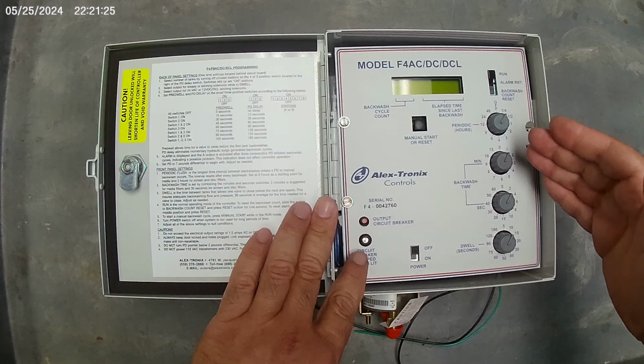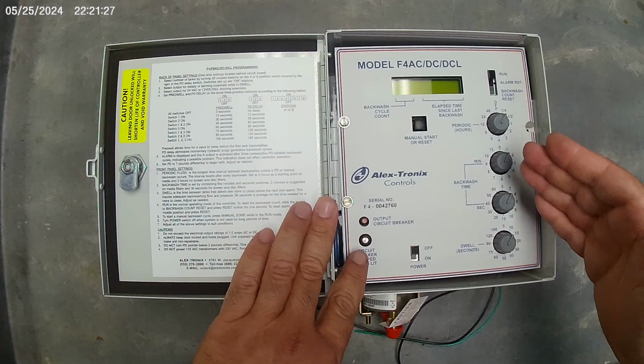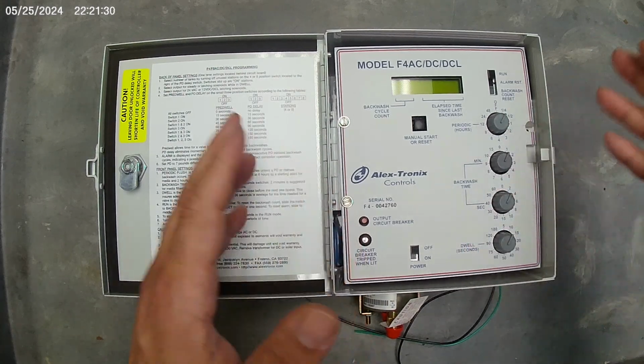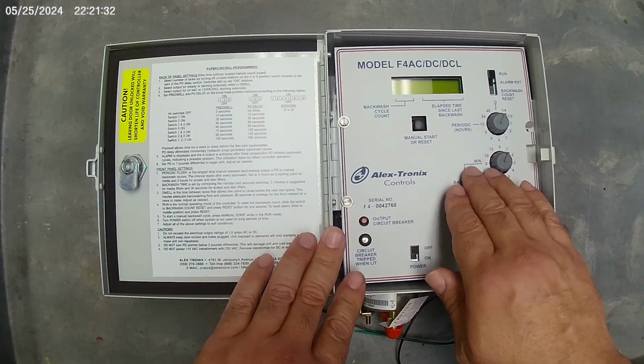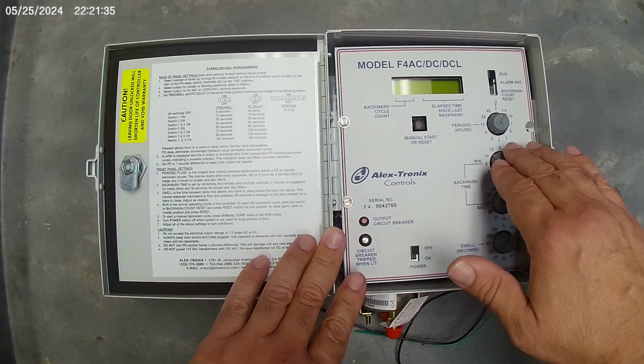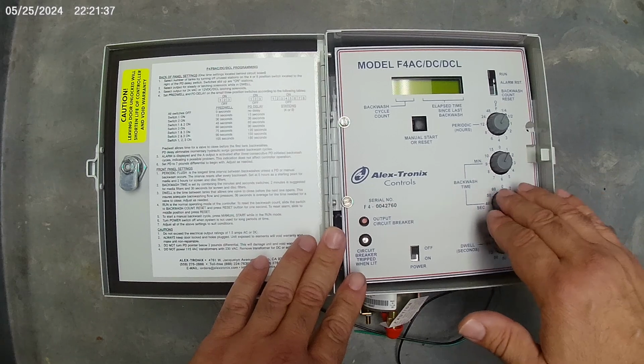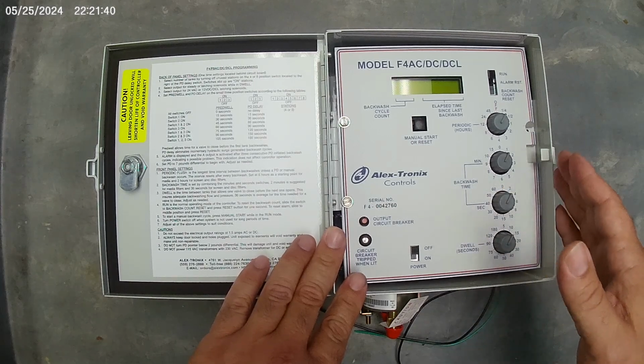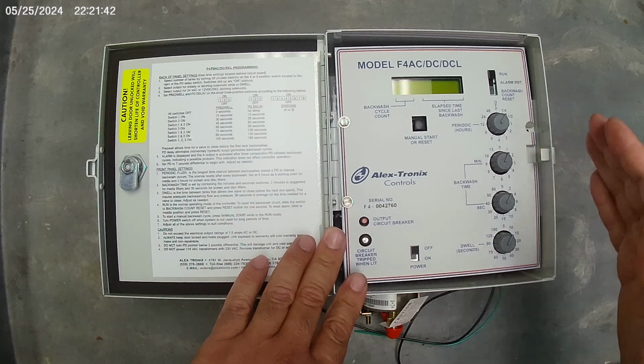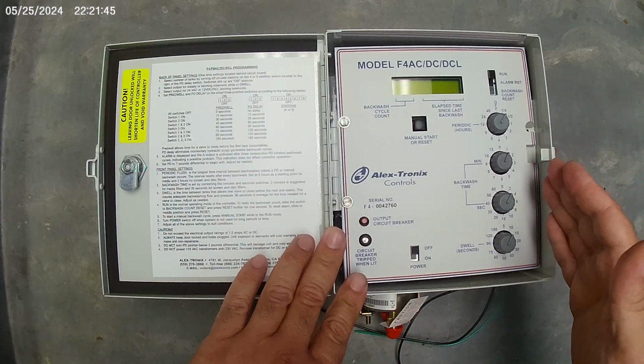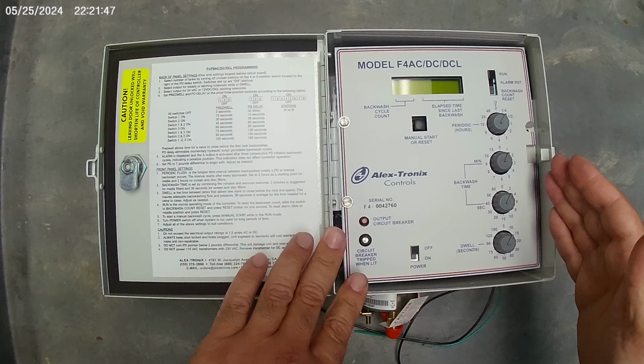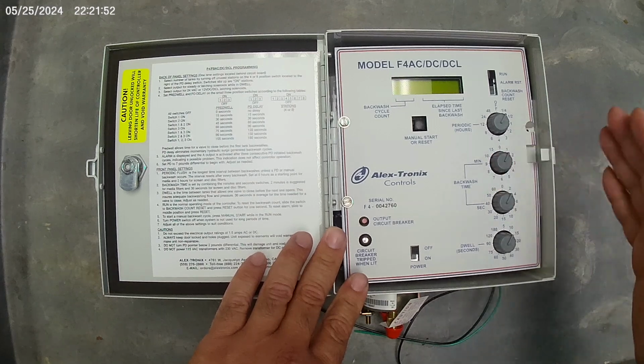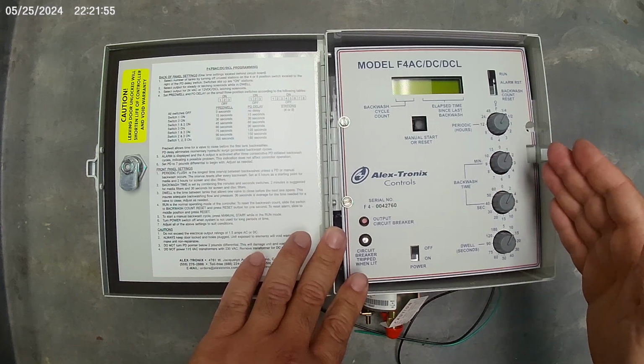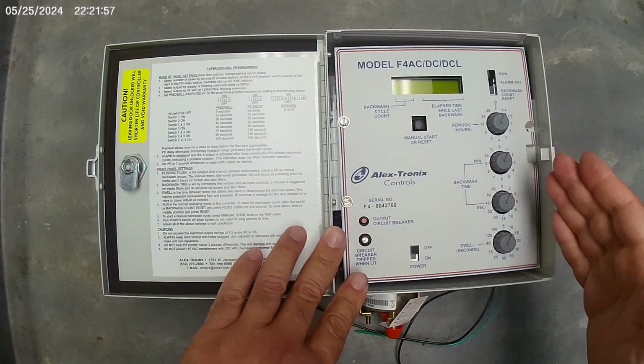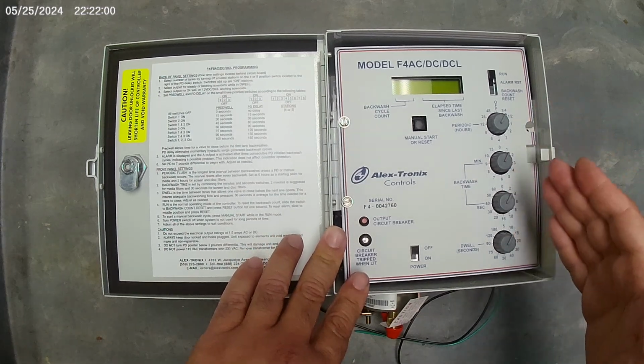In some sand media filters, you may want to flush them periodically just to make sure that the sand does not settle out and impact. Timing selections on these models is adjustable in both minutes and seconds cumulatively. A typical time for a sand media filter might be 2 minutes or 90 seconds flush time. A screen or disc filter may be only 30 seconds or so, and it depends on flow, volume, pressure you have to backflush with, so you'll need to experiment with your own system to determine what works best for you.